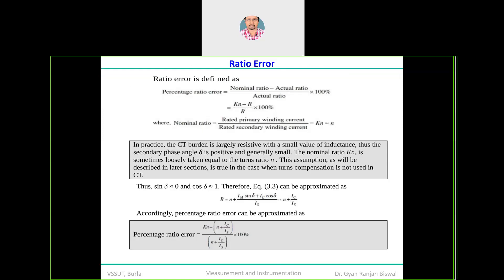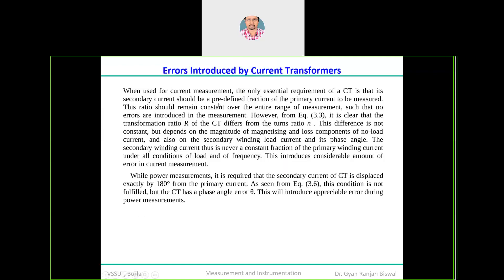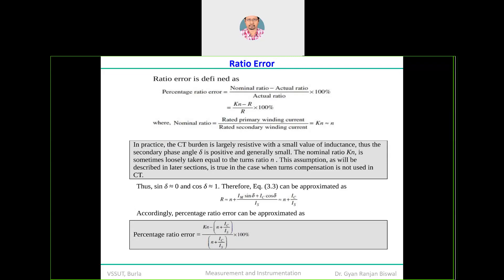There are two different kinds of errors: ratio error and phase angle error. For ratio error, since sin(δ) → 0 and cos(δ) → 1, the transformation ratio R = N + (IC / IS). Substituting this gives the percentage ratio error. For phase angle error, substituting from equation 3.6: theta ≈ (180/π) × [IM·cos(δ) − IC·sin(δ)] / (N·IS). With sin(δ) → 0 and cos(δ) → 1, theta ≈ (180/π) × (IM / N·IS) degrees. These equations can be used directly to calculate numerical values.